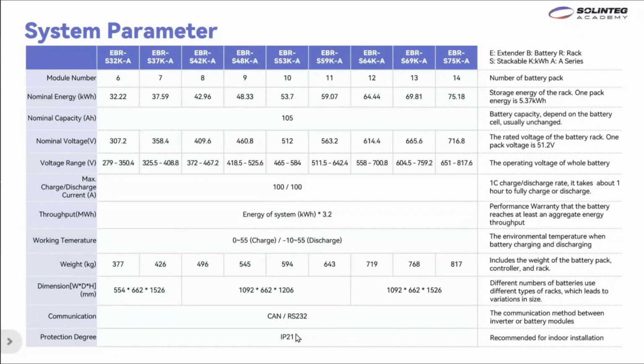The battery just has IP21. The 2 means it can protect against solids within 12.5 millimeters, and the 1 means it can only protect against water dropping vertically from the top. So we recommend it for indoor installation only.